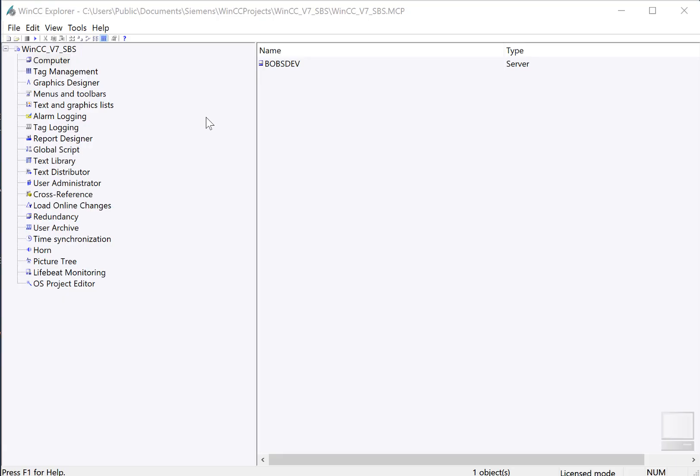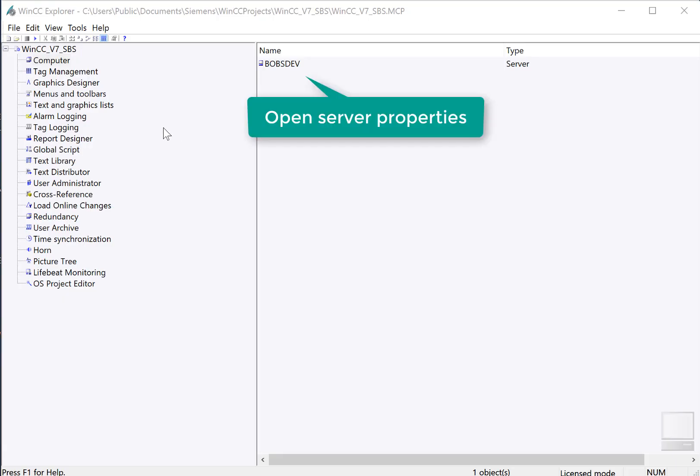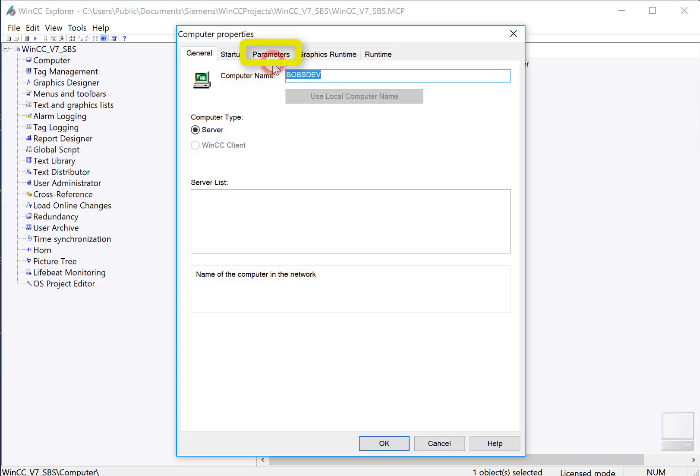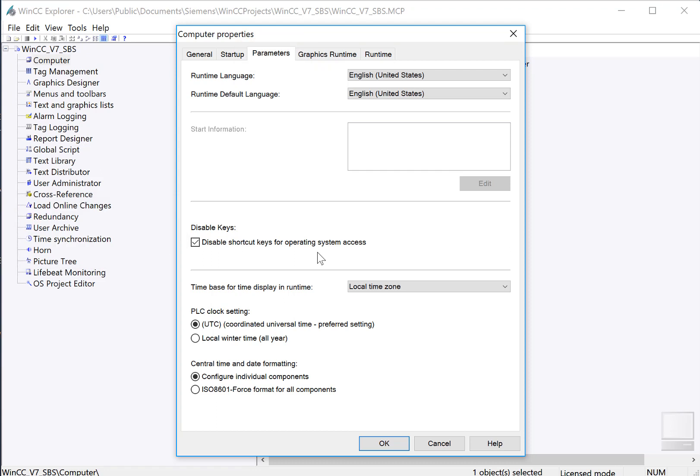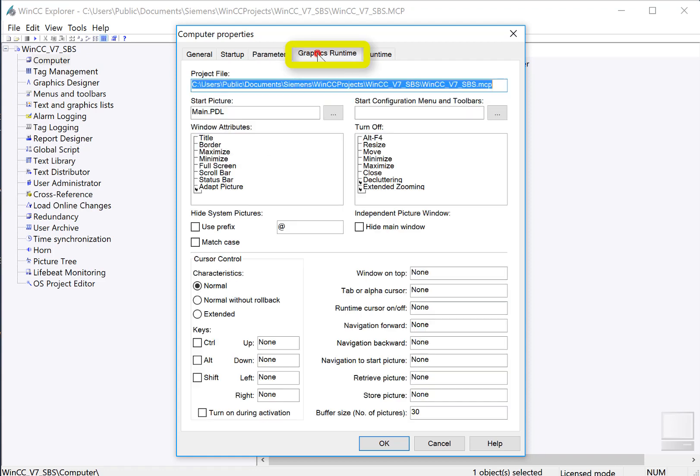Now let's go to WinCC Explorer, and we'll secure our project for runtime. I'll click computer and double-click my server name. On the parameters tab, we're going to check disable shortcut keys for operating system access. This disables keyboard shortcuts that would allow operators to get to the operating system, like Control-Alt-Delete, Alt-Tab, and things like that.